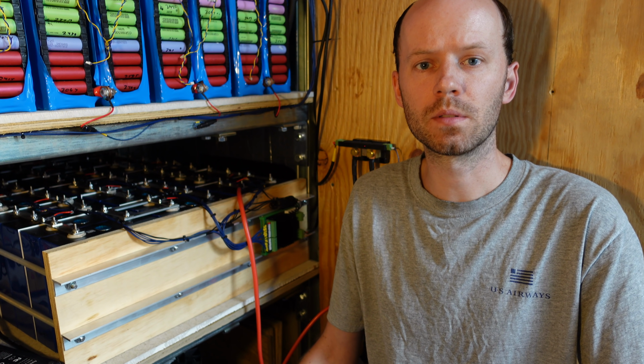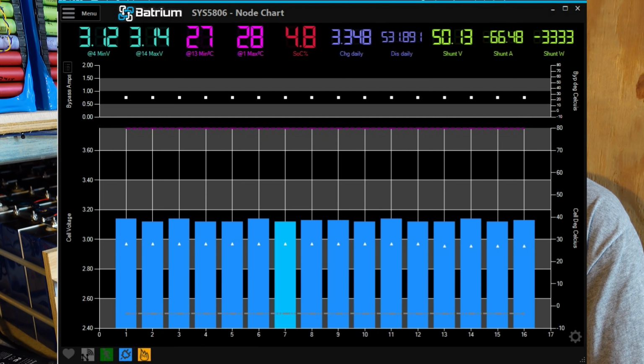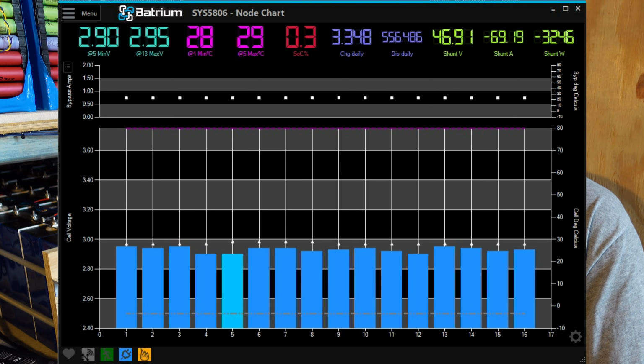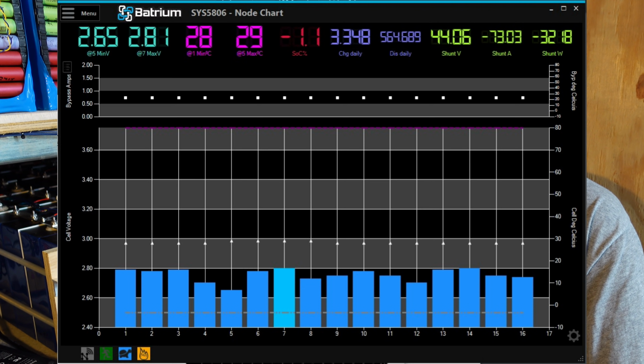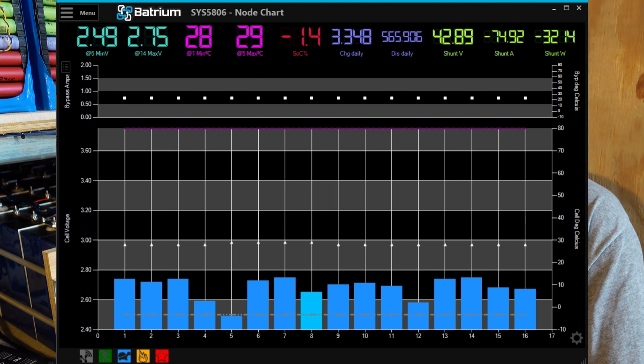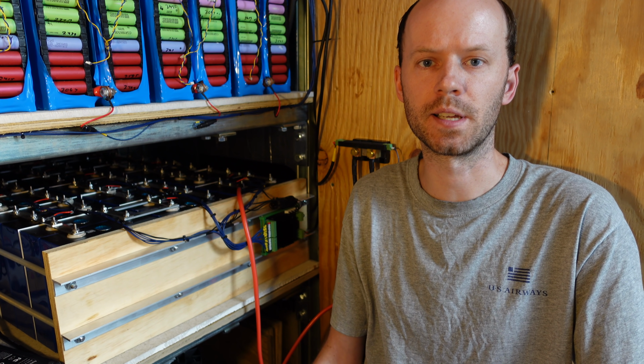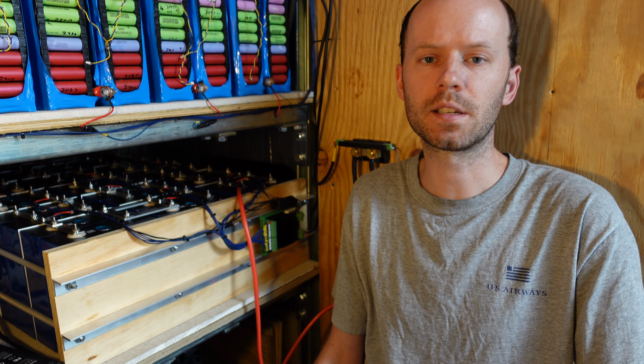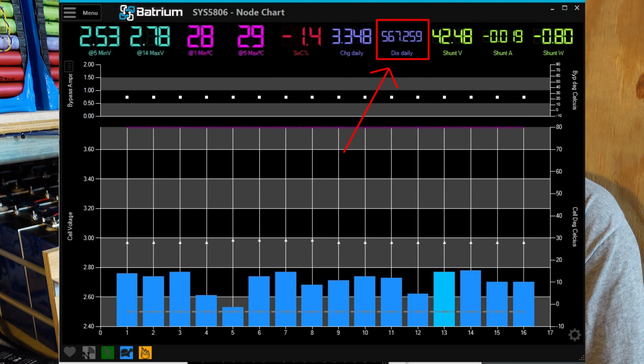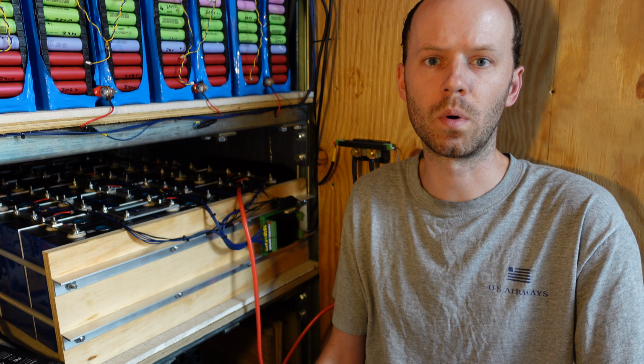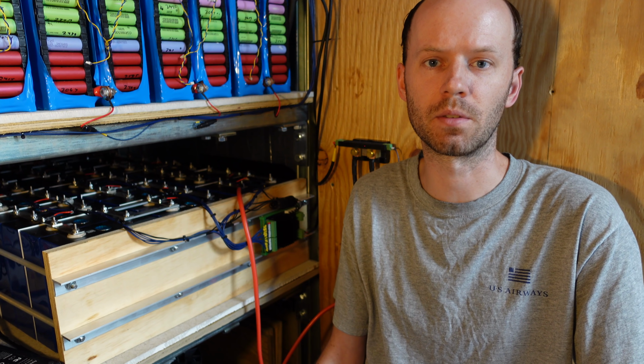Around 3 volts is where the cells really begin to deviate more. Above 3 volts there was a spread of 0.02 volts, then as soon as they dropped below 3 volts it widened to 0.05 volts. As the first cell approached 2.65 volts, the spread widened to 0.16 volts, and ended up at 0.26 volts once the first cell reached 2.5 volts, which was the load disconnect as specified by the datasheet. The test concluded with a final capacity of 567 amp hours, or 101.5% of their rated capacity.